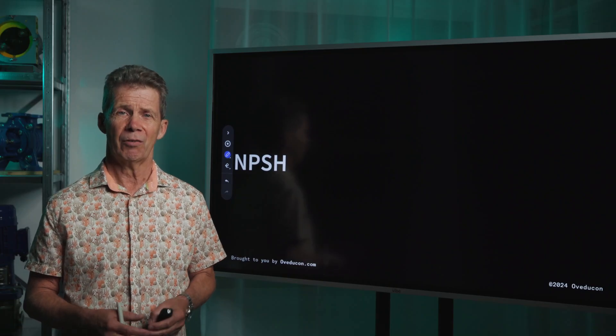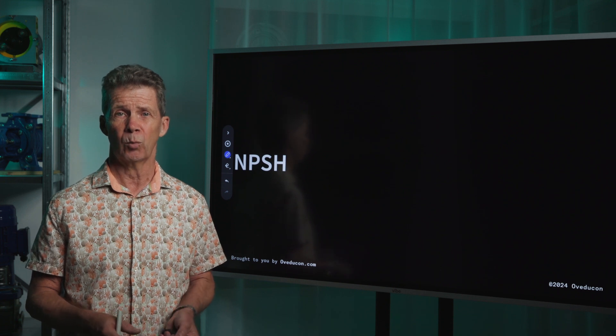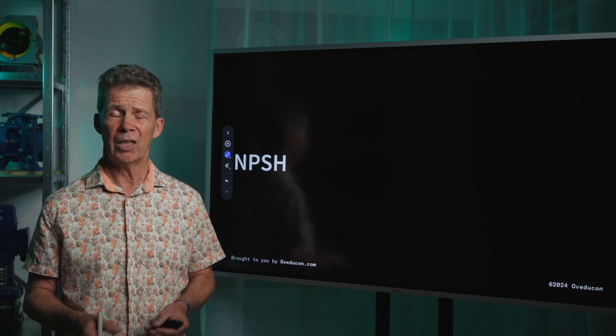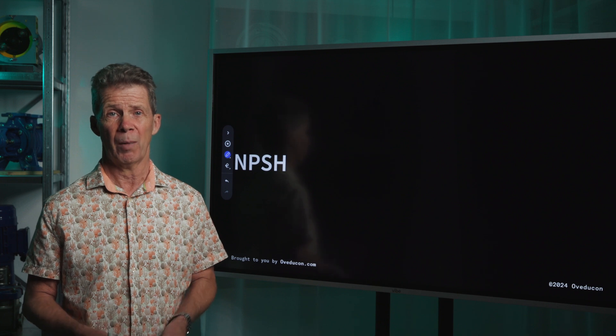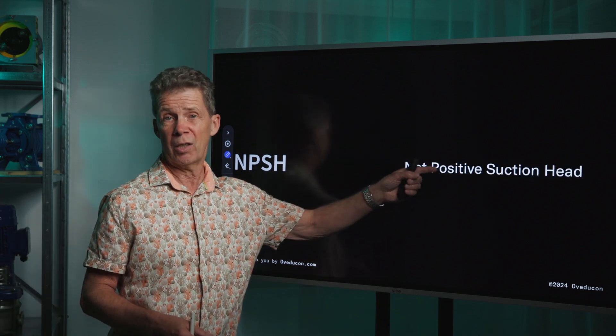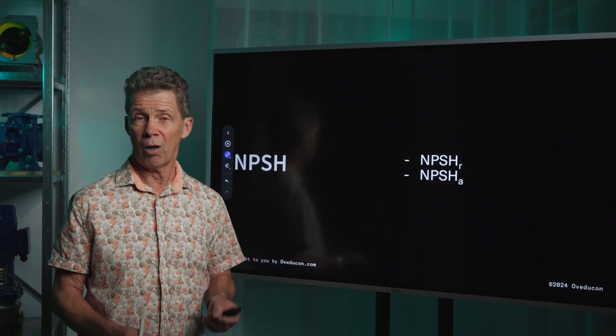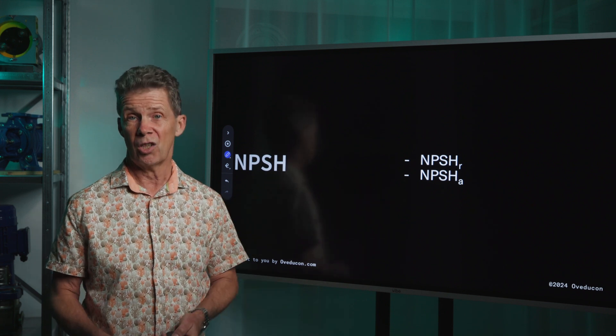In my career I have had to answer many questions about the meaning of the word NPSH and its purpose when sizing a pump. NPSH stands for net positive suction head. In the pump industry we normally work with two different NPSH values. You have the NPSH-R and the NPSH-A.